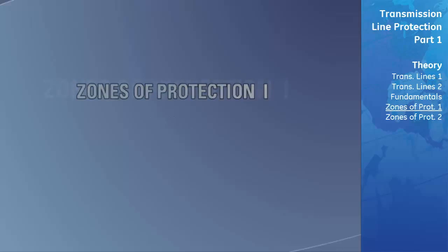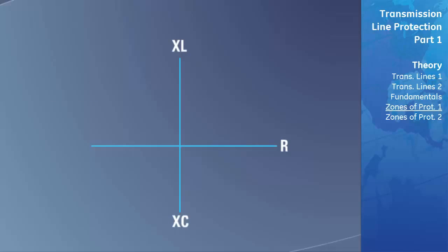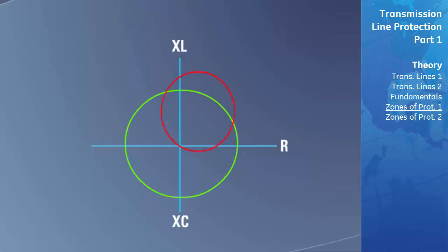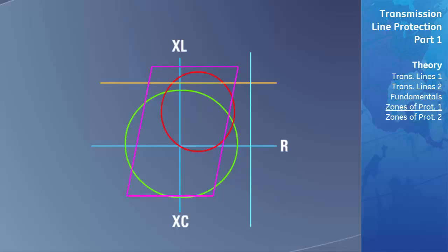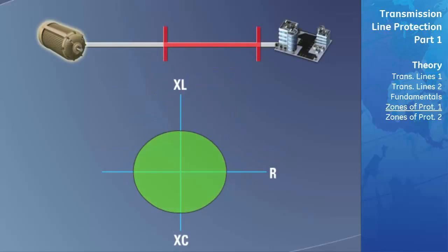To program distance relays, you need to configure the impedance of the line where any impedance less than this value will indicate a faulted line. This is done in modern distance relays by creating zones of operation on the RX diagram. If the impedance calculated ever falls within this zone, the relay will trip. These zones fit into the following operating characteristics: an impedance zone, an admittance or Mho circle zone, a reactance zone, a resistance zone, and a quadrilateral zone.